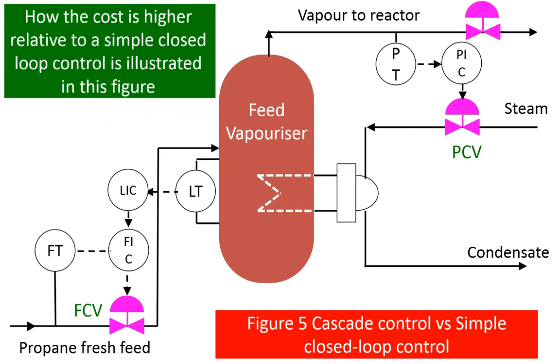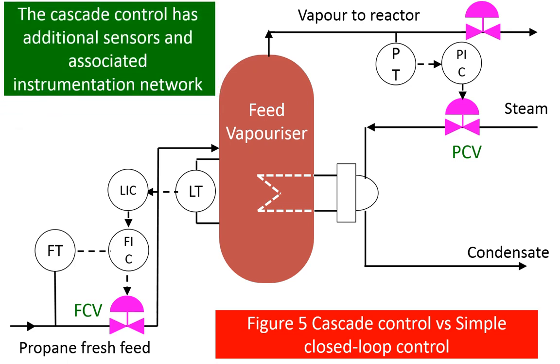How the cost is higher relative to a simple closed loop control is illustrated in this figure. The vaporizer pressure control is a simple closed loop control, while the level control is a cascade control. The cascade control has additional sensors and associated instrumentation network, hence the total installation cost will be higher.